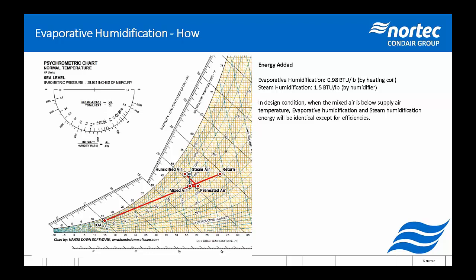So in this situation, again, this is basically the design case situation, where we've got your coldest outside air and your return air is, again, around 71, 72 degrees. So if you're familiar with psych charts, you know that when you mix outdoor air, or mix two air streams, the mixing point is somewhere along the straight line between the two. In this case, our minimum outside air happens to bring us pretty much to 55 degrees, just a little bit higher, actually.